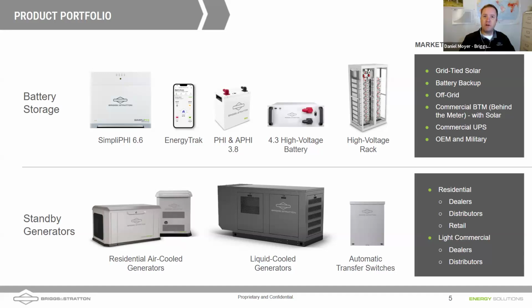One quick comment on the generators, Nathan, is that the liquid cooled generators come in 480 or 208 3-phase. So that's a really nice advantage for the light industrial commercial as well. The air cooled come in 13, 18, 20, 22 and 26K, and they are all 240 split phase.